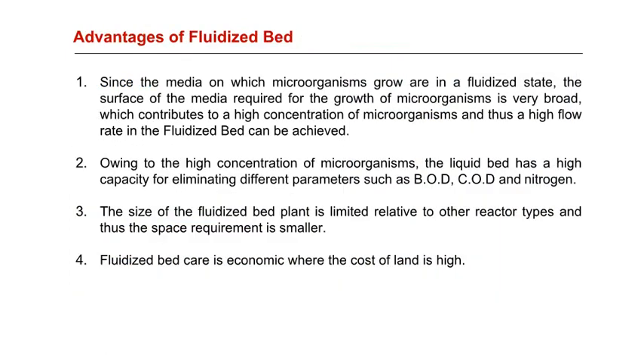The advantages of the fluidized bed compared to conventional trickling filters are as follows. Since the media on which microorganisms grow are in a fluidized state, the surface area required for the growth of microorganisms is very broad, which contributes to a high concentration of microorganisms and thus a high flow rate in the fluidized bed can be achieved. Owing to the high concentration of microorganisms, the fluidized bed has a high capacity for eliminating different parameters such as BOD, COD, and nitrogen. The size of the fluidized bed plant is limited relative to other reactor types, and thus the space requirement is smaller. Fluidized bed treatment is economical where the cost of land is high.